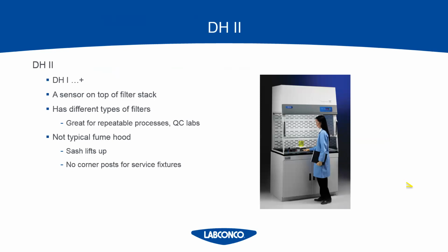The DH2 does have a sensor on top of the filter stack. So it does have the safety feature of a sensor. However, because it's on top of the filter stack, once that sensor goes off, the filters need to be replaced immediately. The DH2 enclosures also have application-specific filters, just like the DH1 hood, such as formaldehyde, ammonia, organic vapor. They have acid sulfur, a couple different types of filters. And since these have a sensor on top of the filters, they're really best for repeatable processes when you can tell how long the filters are going to last.